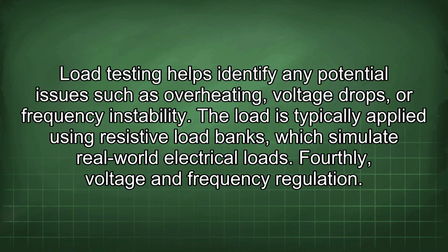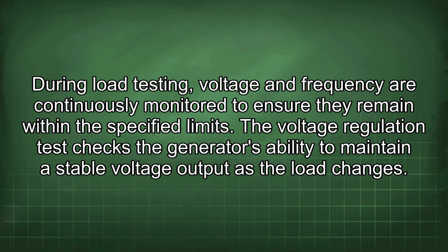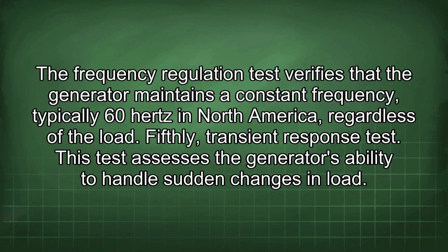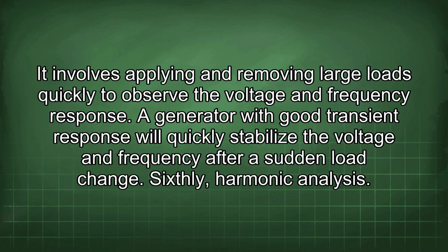Fourthly, voltage and frequency regulation. During load testing, voltage and frequency are continuously monitored to ensure they remain within the specified limits. The voltage regulation test checks the generator's ability to maintain a stable voltage output as the load changes. The frequency regulation test verifies that the generator maintains a constant frequency, typically 60 Hz in North America, regardless of the load. Fifthly, transient response test. This test assesses the generator's ability to handle sudden changes in load. It involves applying and removing large loads quickly to observe the voltage and frequency response. A generator with good transient response will quickly stabilize the voltage and frequency after a sudden load change.